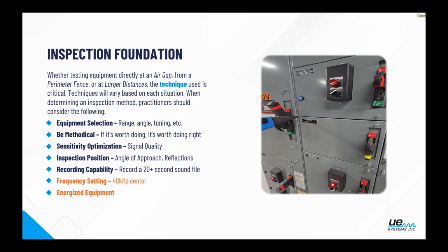And the most critical thing for ultrasound inspection is making sure that we are actually listening at the right frequency. Any ultrasound probe that's being used for an electrical inspection should always be centered at 40 kilohertz. There's no reason to move that around. So just before you even start sweeping, make sure your sensitivity is dialed in and your frequency is correct.